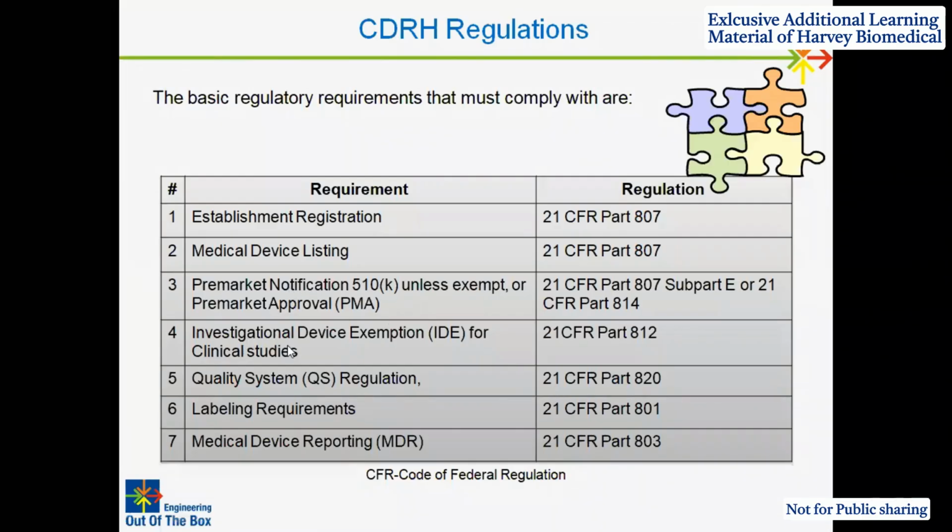This is IDE, investigational device exemption. As I told, IND is the investigational new drug application. The same way here also, IDE, investigational device exemption, for clinical studies. For some clinical studies we have to take an exemption. That is 21 CFR Part 812. All these 21 CFR parts are available on the USFDA site, where we can verify all the classes.